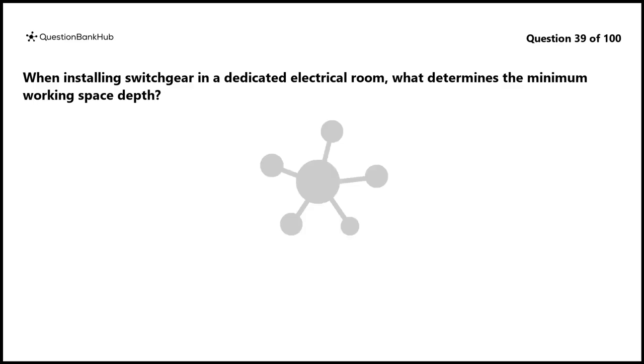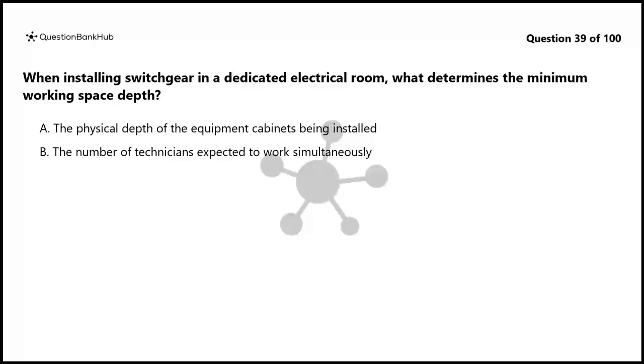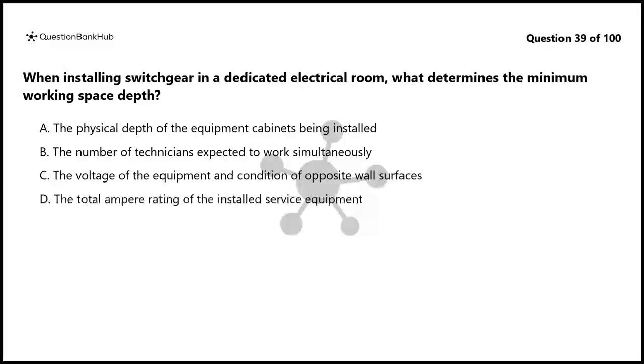Question 39. When installing switchgear in a dedicated electrical room, what determines the minimum working space depth? A. The physical depth of the equipment cabinets being installed. B. The number of technicians expected to work simultaneously. C. The voltage of the equipment and condition of opposite wall surfaces. D. The total ampere rating of the installed service equipment.